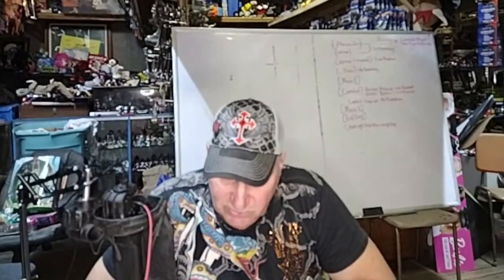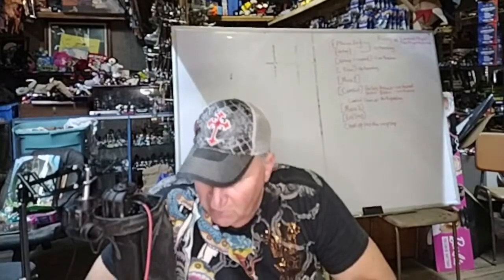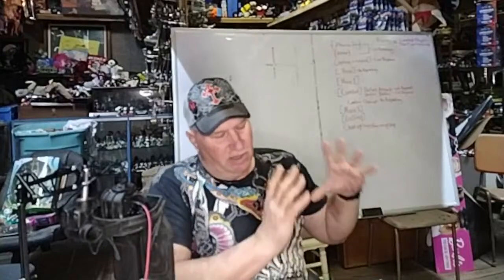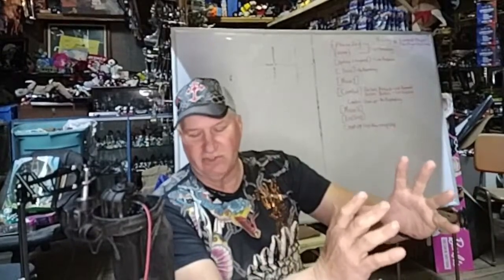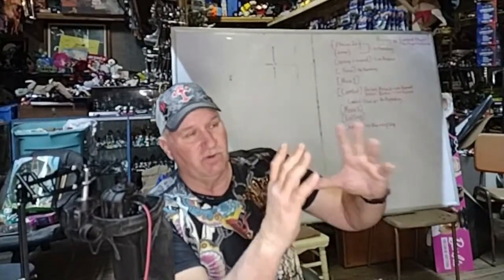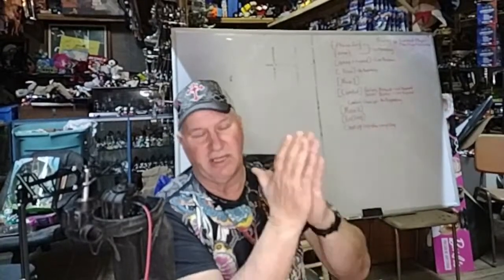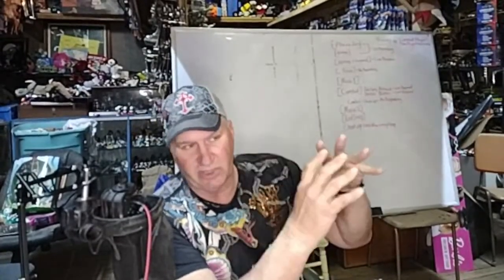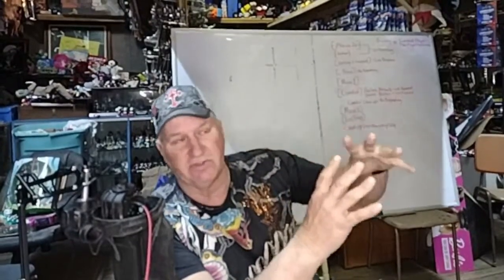What I suggest is, if your master bedroom is all the way to the end of the house, a double wide or any single wide mobile home has this unique problem. And in a house, what you do is you take a larger ductwork, say 14-inch, and the further away you get from the main source of your central heat, the smaller and smaller the ductwork gets, and that keeps, sort of like hydraulics, your air pressure higher or at the same amount the further away it gets. So you reduce your ductwork. You're not doing that with your double wide or your single wide. It's the same size all the way.